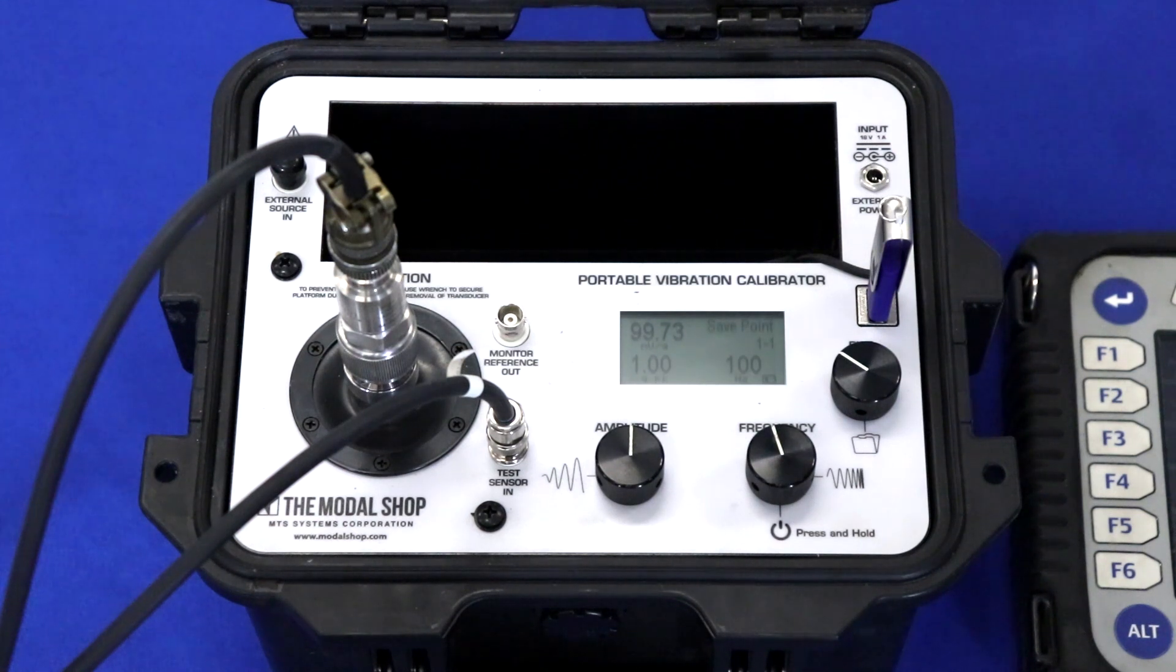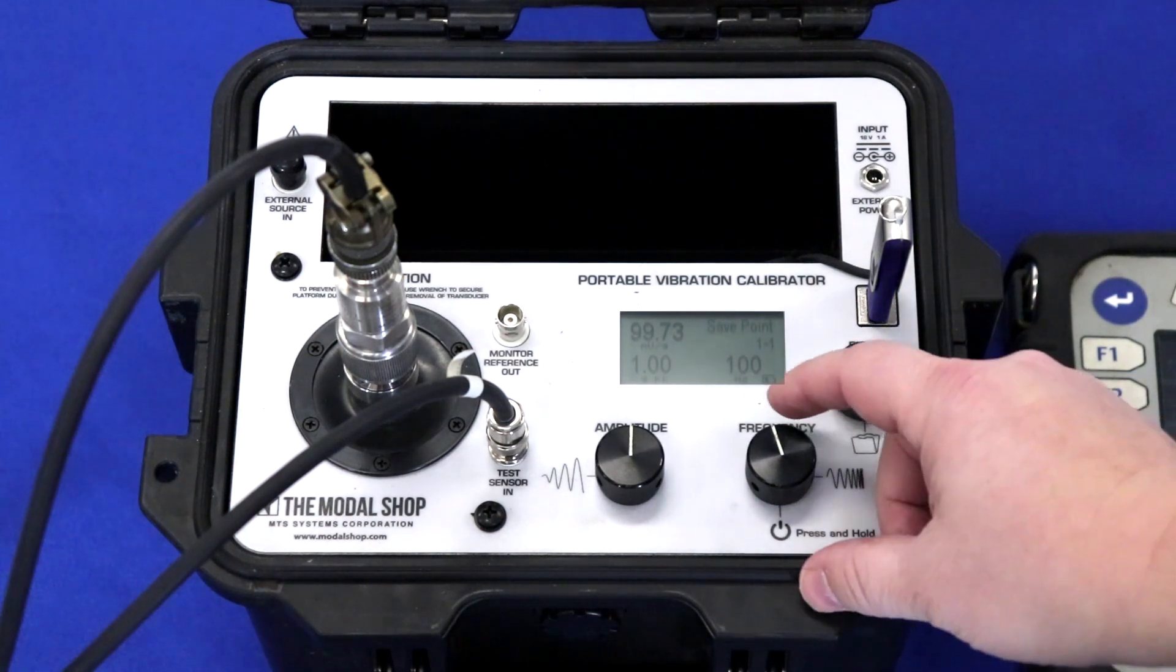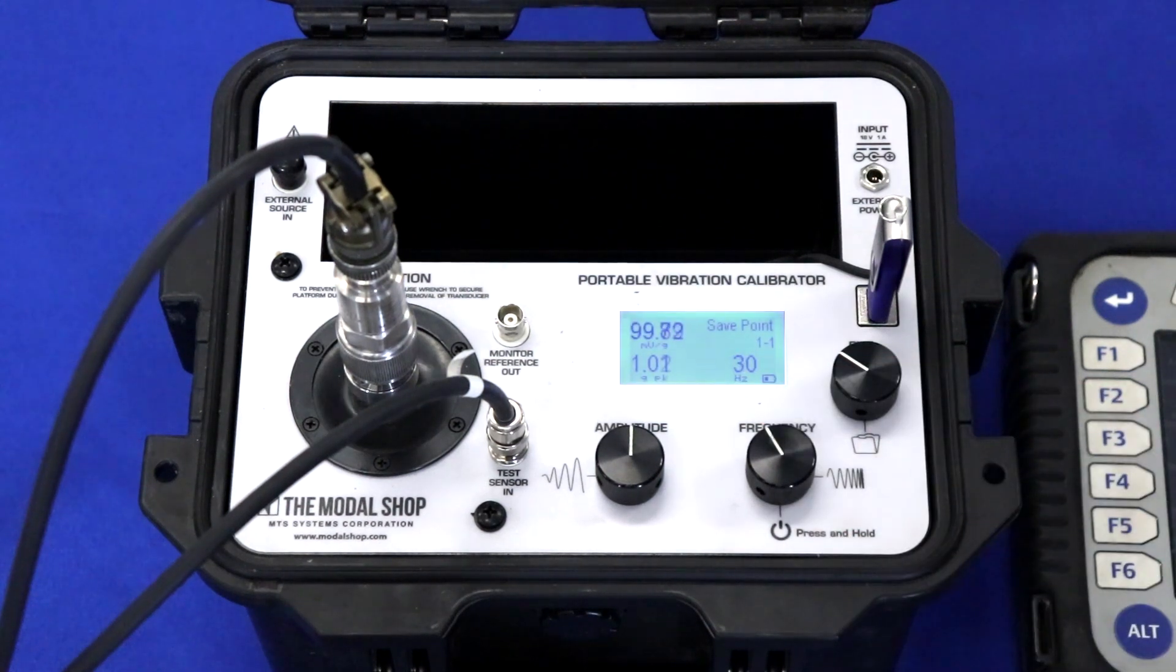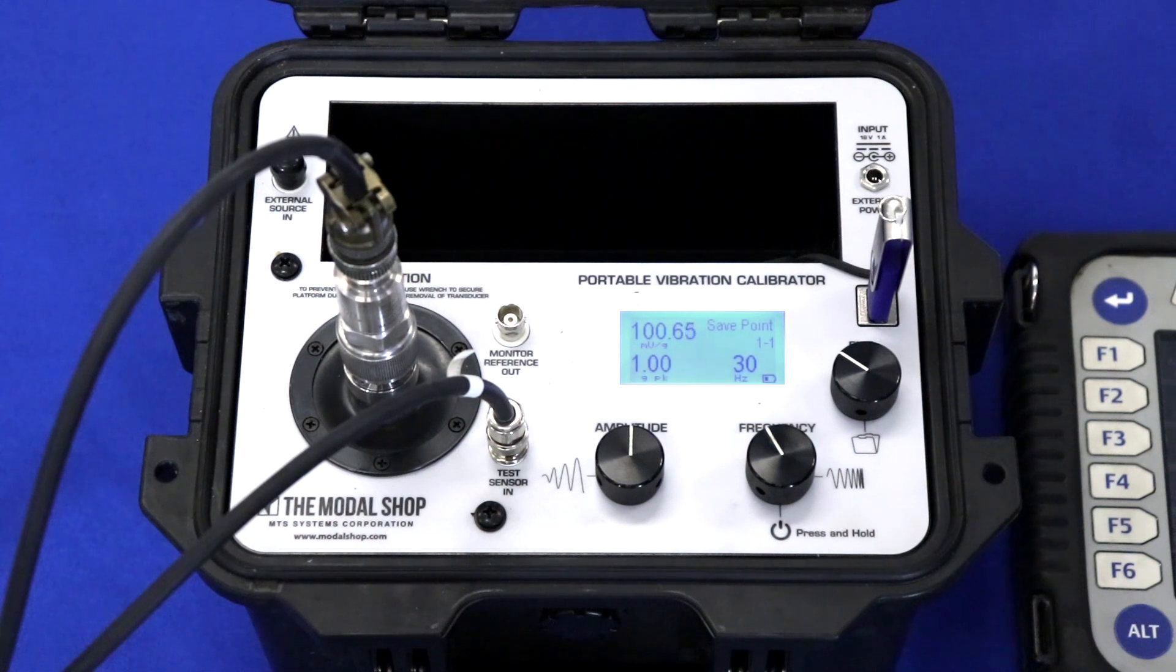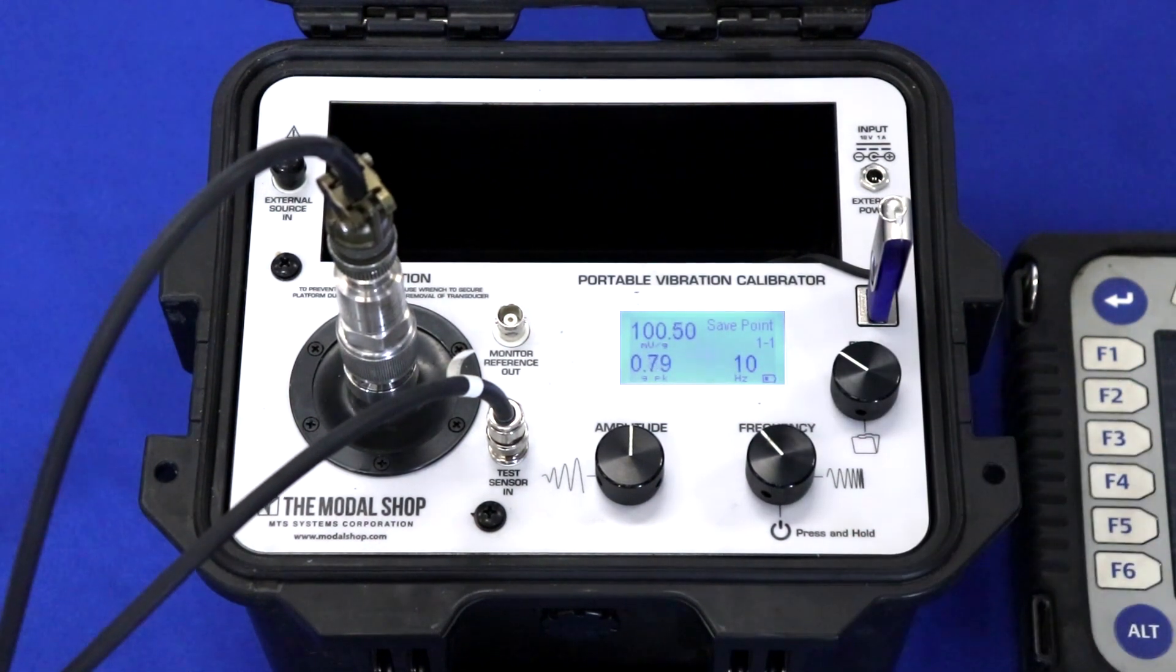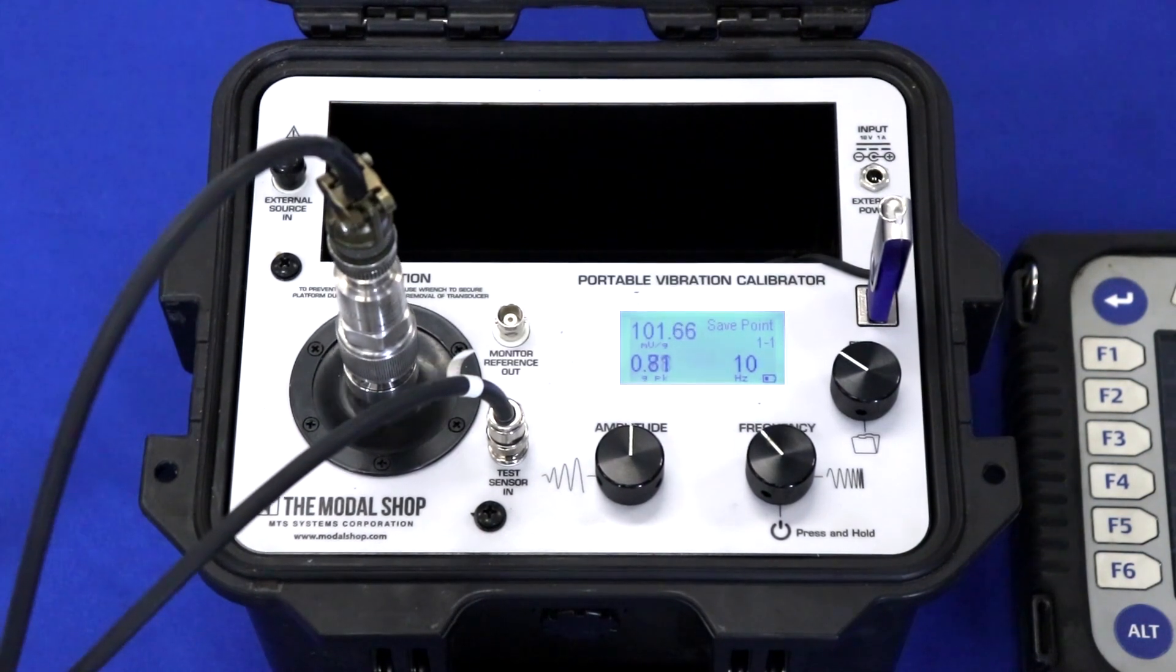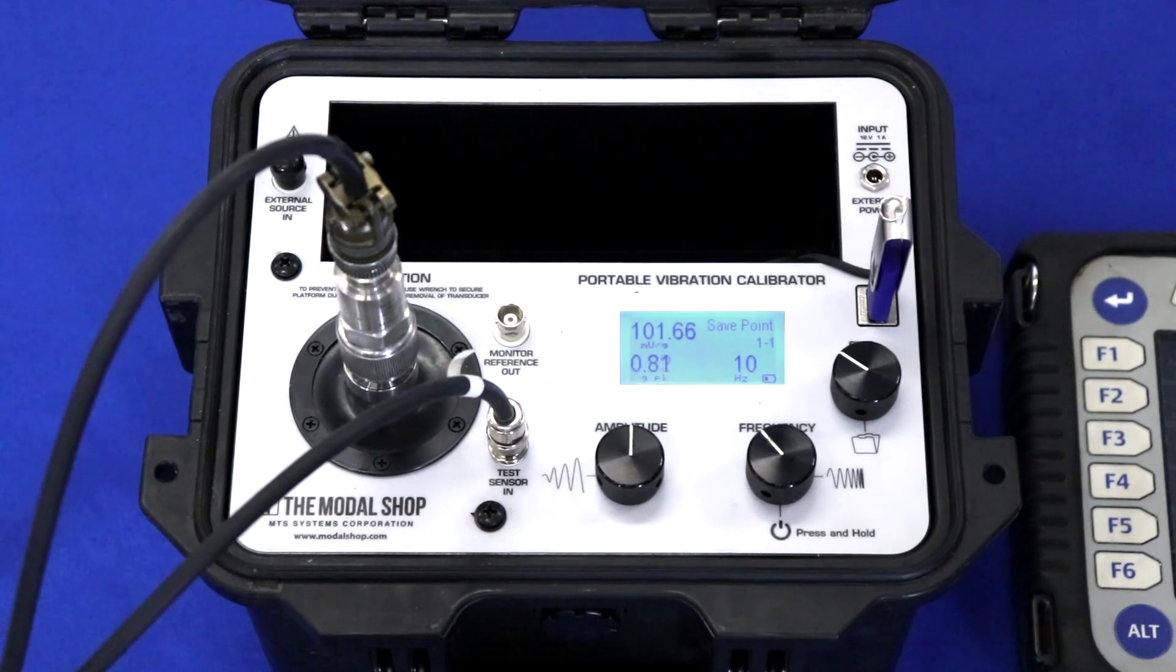We also want to test this transducer at some other frequencies of interest. So let's go down to 30 hertz and check it at 1 G peak. You can see that the accelerometer is still 100 millivolts per G. At 10 hertz, the accelerometer is about 102 millivolts per G at 101.6.